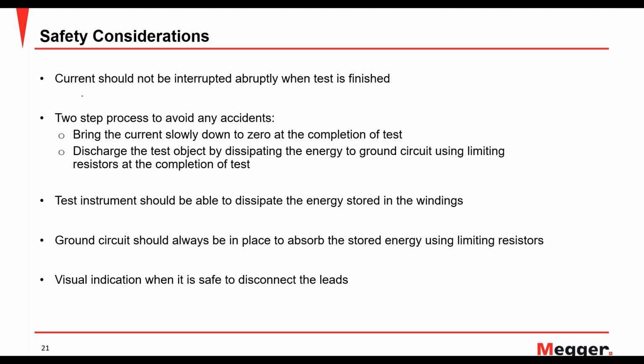Now, these are all the safety considerations, so very important. Current should not be interrupted abruptly when the test is finished. You need to leave the current discharged. The safest way to do it is to bring the current down slowly to zero, and after completion of the test, discharge the test object by dissipating everything to ground using limiting resistors. This is all done internal to the instrument itself, but it is necessary to know what's happening behind the scenes when you complete the test.